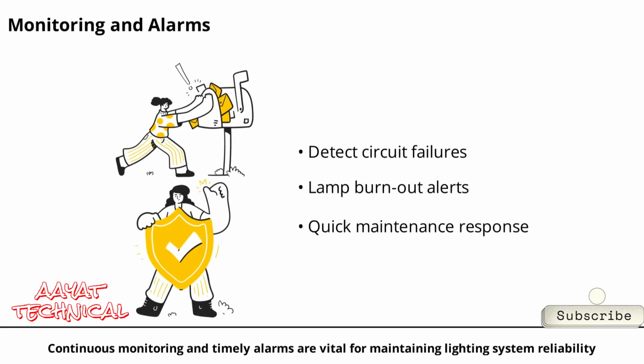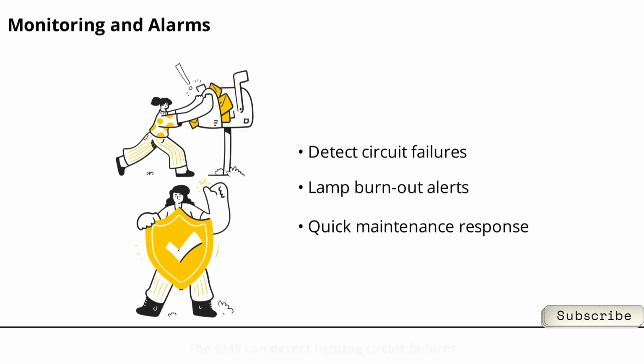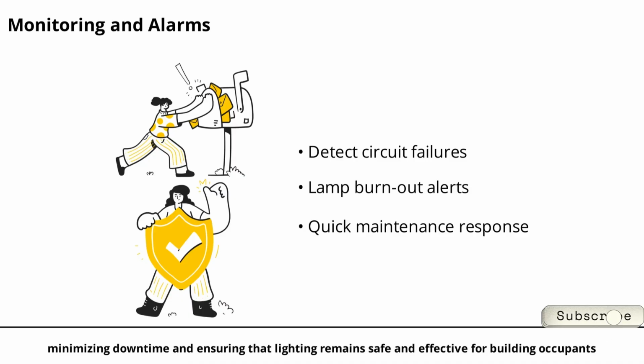Continuous monitoring and timely alarms are vital for maintaining lighting system reliability. The BMS can detect lighting circuit failures, lamp burnouts using current sensing, relay module overloads, and even tamper alarms if a panel door is opened. These alerts enable quick response and maintenance, minimizing downtime and ensuring that lighting remains safe and effective for building occupants.